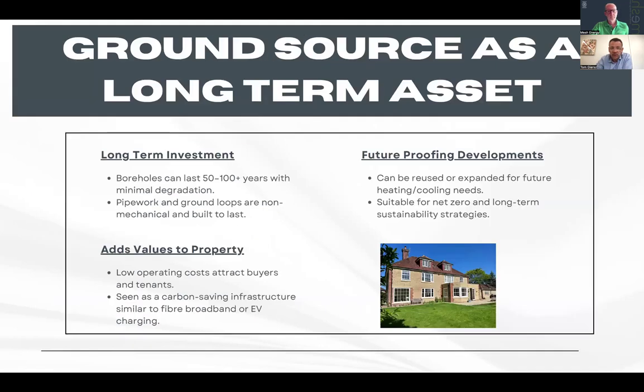And ground source heat pump as a long-term asset. So it's a long-term investment. Boreholes can last a long time. The pipes will last 50 to 100 years. They've got minimal degradation, they're not exposed to UV, and you are future-proofing your developments.